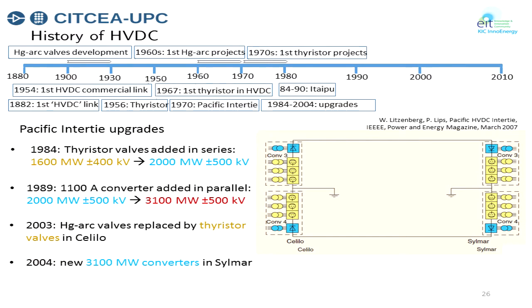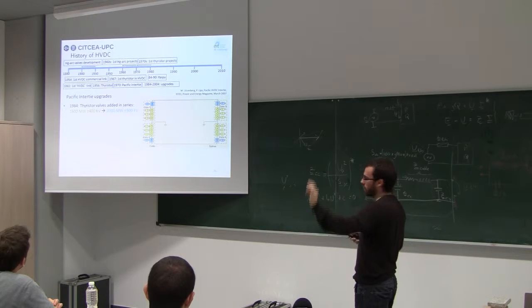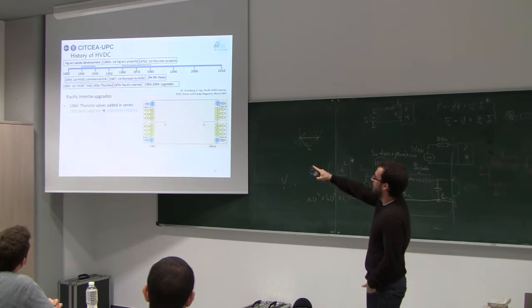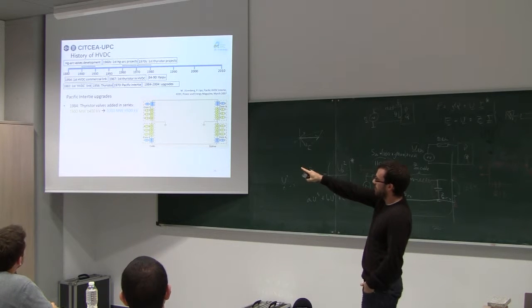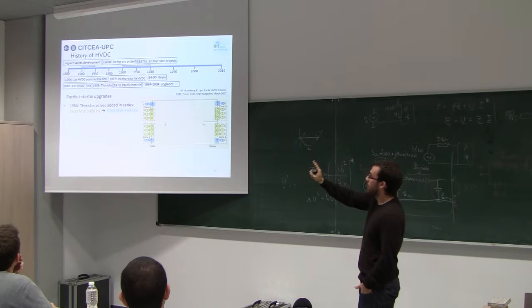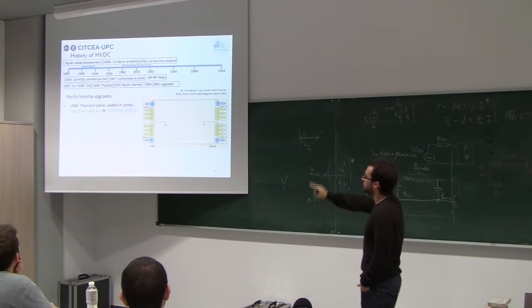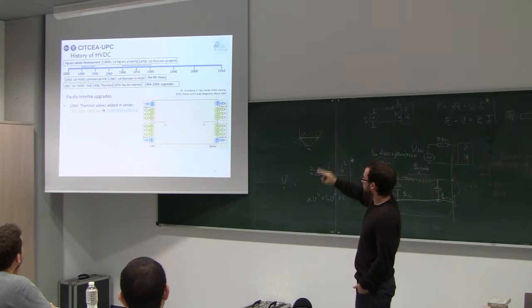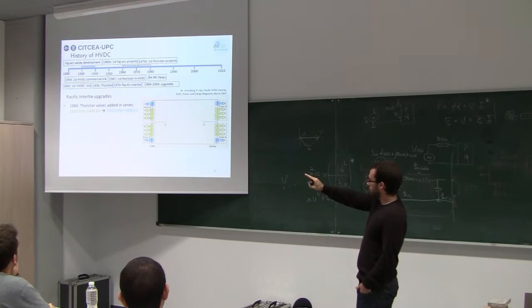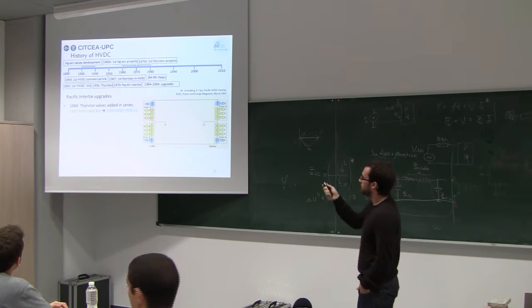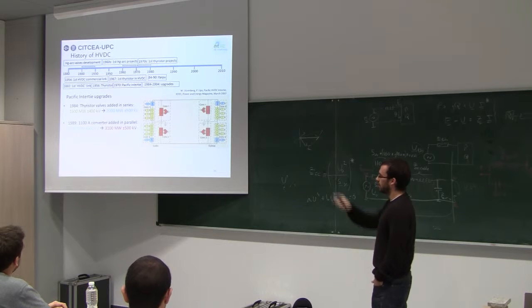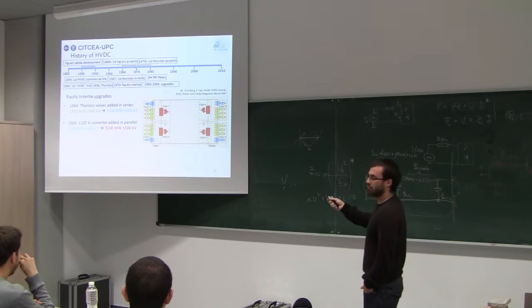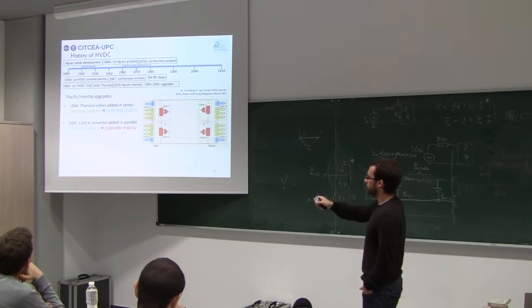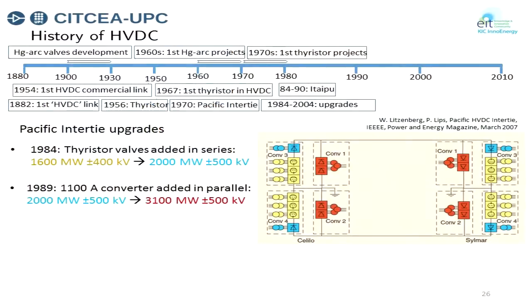More upgrades: the Pacific Intertie, the link on the west coast of the US. They just had valves, and reached 2,000 megawatts by installing thyristors in series, increasing the voltage and power to that value. Five years later, they installed converters in parallel, so they could increase the current, keeping the voltage the same.